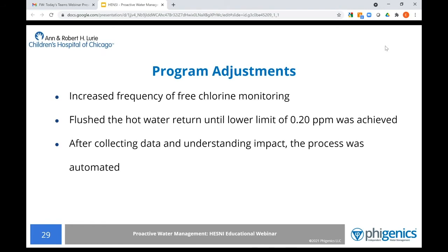Over a period of months, we reviewed the testing and looked for patterns. This type of flushing was primarily somebody going around and flushing the actual sink fixtures, shower fixtures, etc. Frankly, we struggled through the first 12 to 18 months of the program. This was to get the water quality to the level which we expected. We have other water quality programs at our other facilities, and we know what we can achieve.